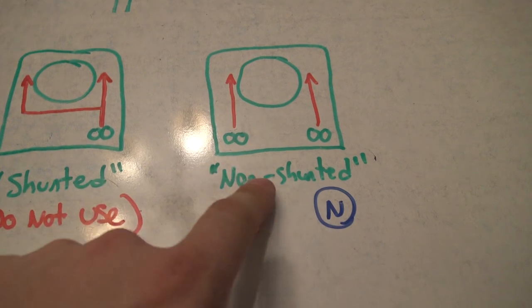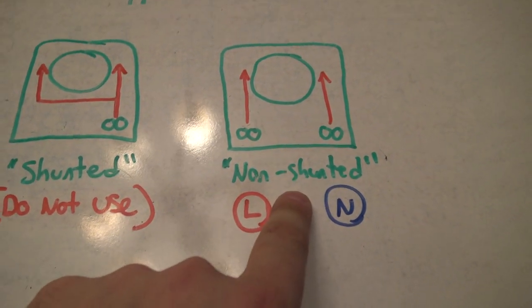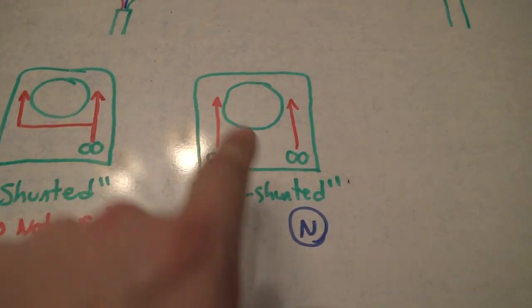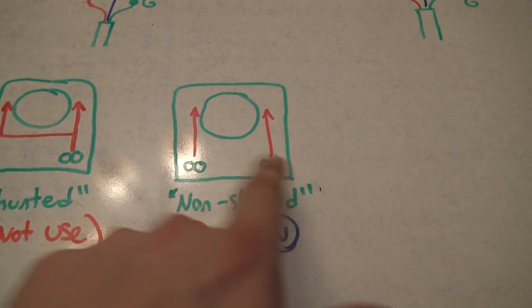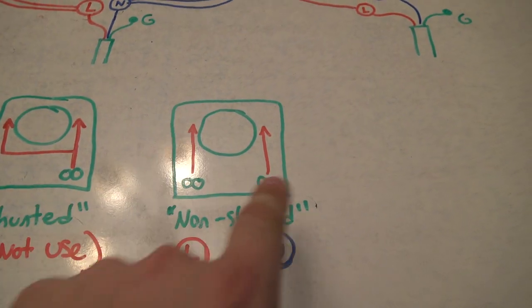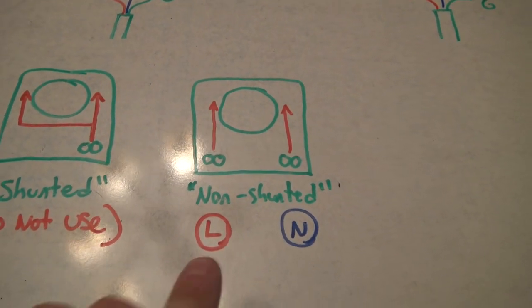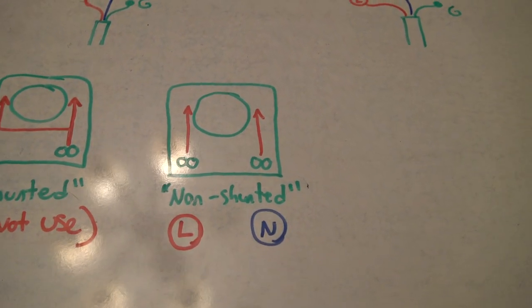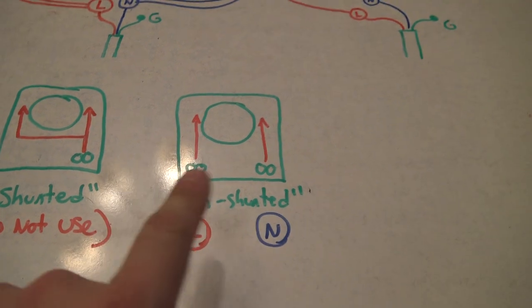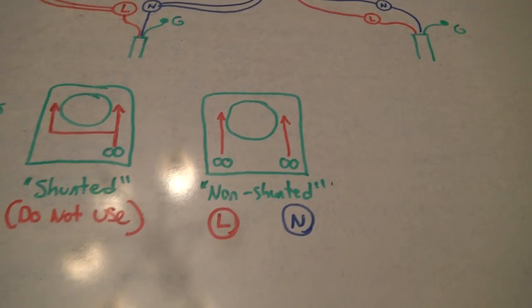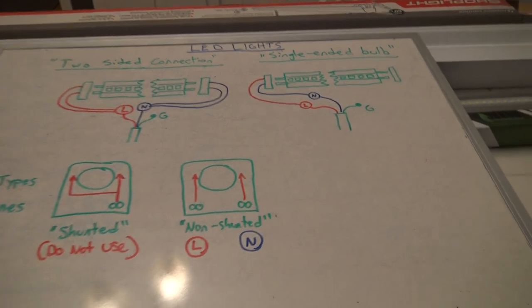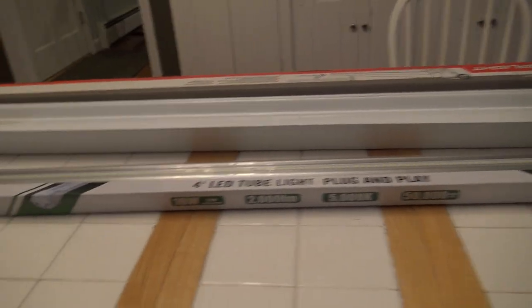The one that you're going to find most often is non-shunted. And essentially, what that means is you've got two wire terminals, one on each side, and it goes to one pin of that tombstone. So you've got your load coming in one side, and your neutral coming in the other side. That's what you're going to be looking for. That will keep you out of trouble when you are rewiring these fixtures for LEDs.